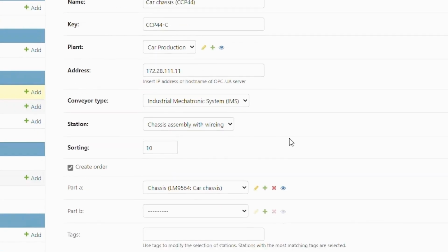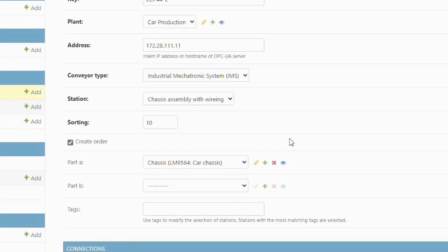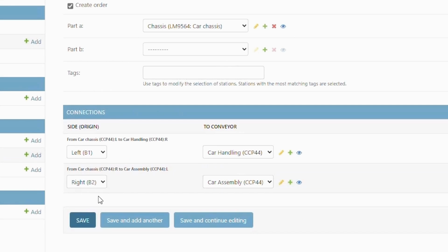Subsequently, we can adjust the belt and station type again. Through sorting, the display order in SCADA is adjusted. Create order refers to the first belt in the production line. Under Part A and Part B, the workpieces for the respective station can be added. If the station only has one magazine, we leave Part B empty. At the very bottom under Connections, we can define the structure of the system. If your specific system was not included in the templates, you need to make adjustments here.